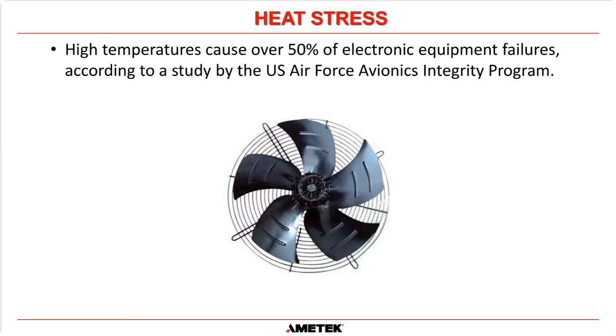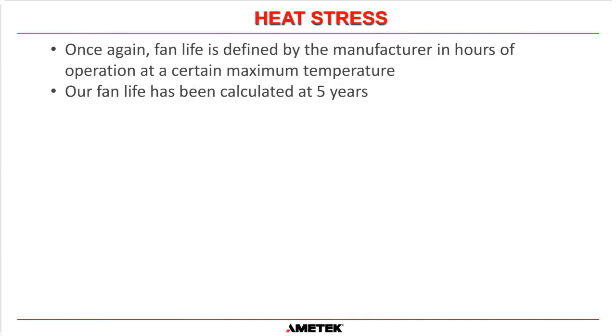So the next thing that we're going to look at is heat stress. High temperatures cause over 50% of electronic equipment failures, according to a study by the US Air Force Avionics Integrity Program. So 50%, that's half of all electronic failures, are caused by heat stress. So it's extremely important that we maintain airflow in our systems, okay? And to do that, our design engineers have to work out what fans are needed and how much air movement is required to get the air out of our UPS systems, exhaust it out into the room, and get it away from our electronic components.